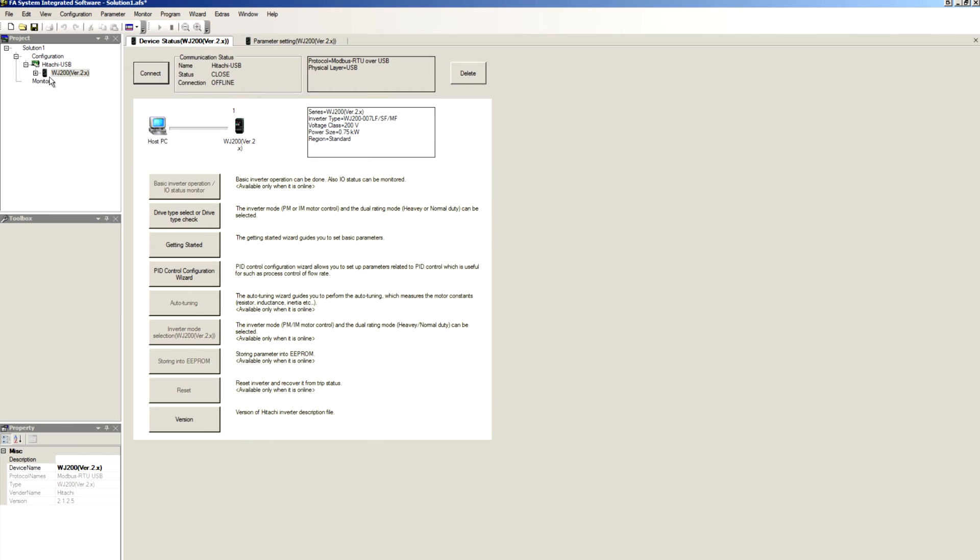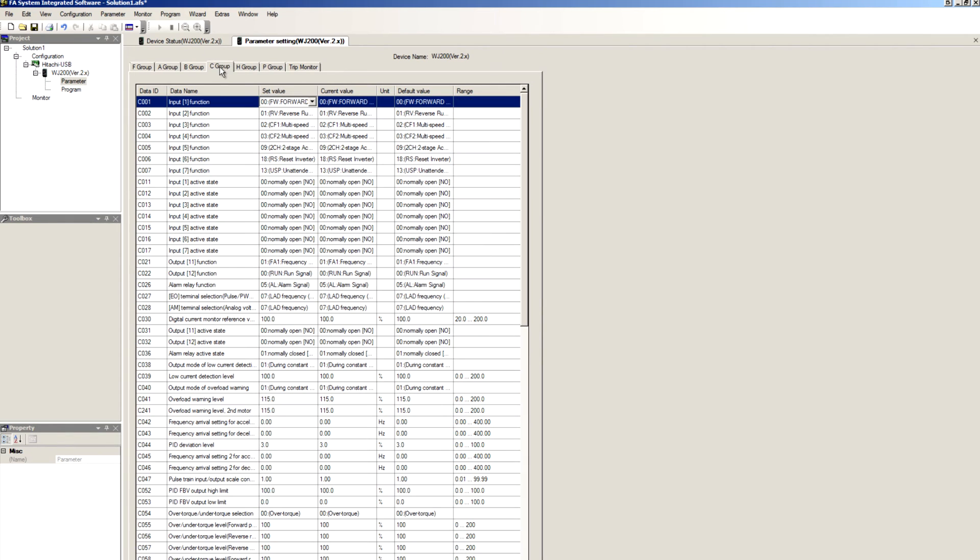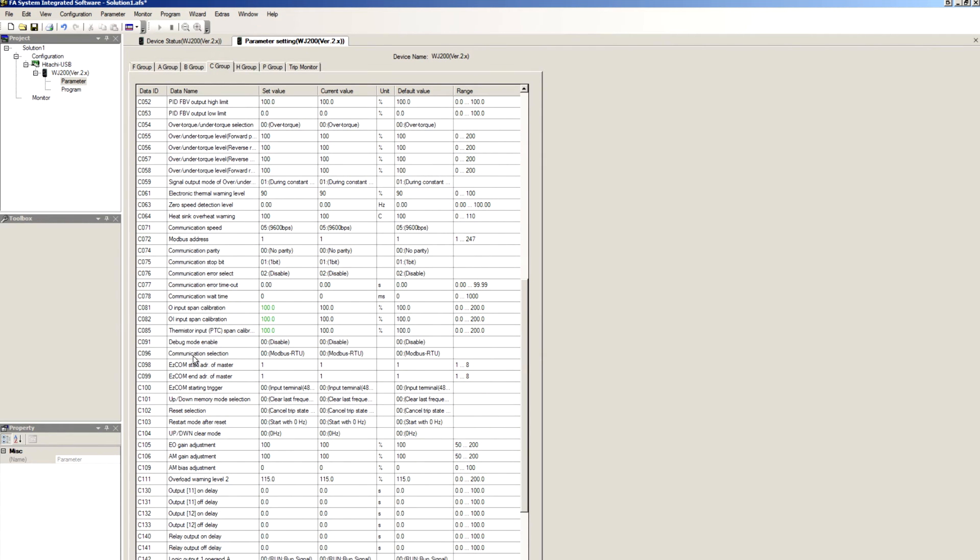First we want to very quickly verify the parameters on the VFD. So we connect to VFD, go to parameters, and in group C, make sure communication selection is set to Modbus RTU, which is the default.